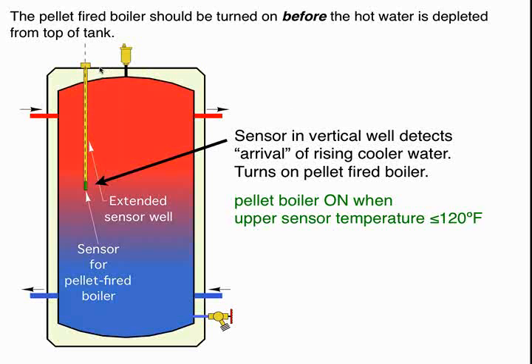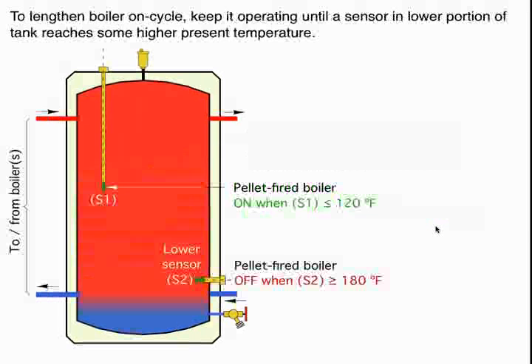Here's our on signal. Again, this could be a Thermocon tank. We have 2 or 3 connections up here at the top that you could thread a well into. And you can see that could be a long temperature sensing well. So we could place the sensor vertically at different heights depending on what our criteria are. But let's say we have a sensor at roughly 60% of the height of the tank, and when that sensor gets down to 120 degrees or less, we're going to turn on the pellet-fired boiler. Okay? So now we're putting heat into the tank, and we're going to continue putting heat into the tank until we get this situation.